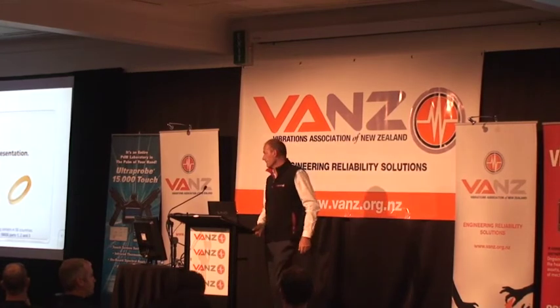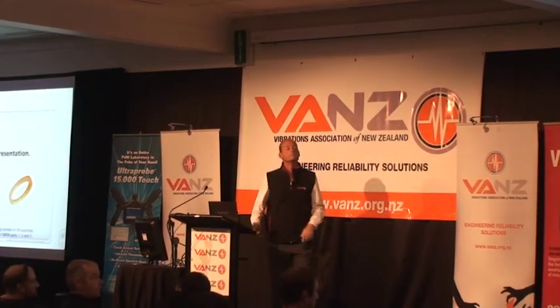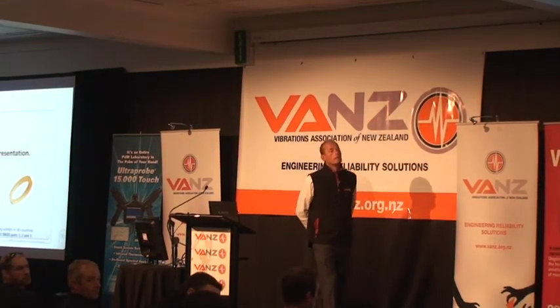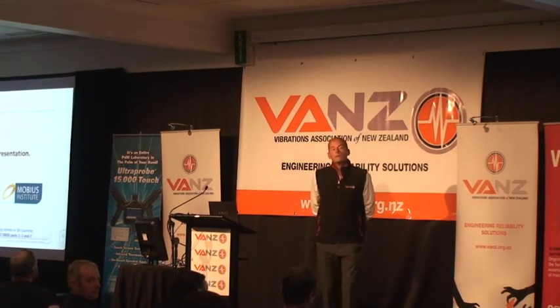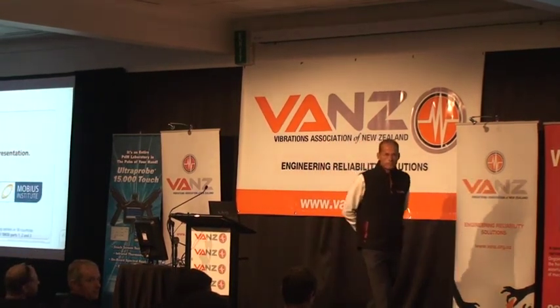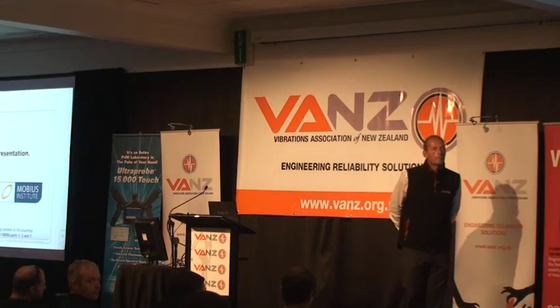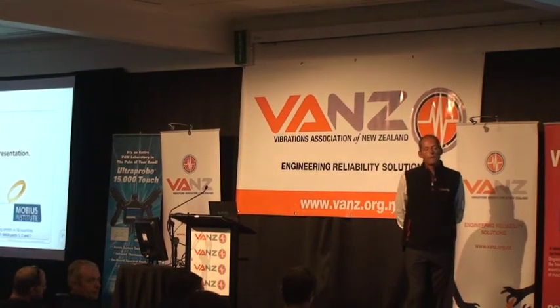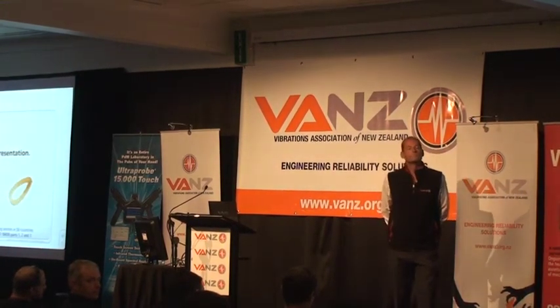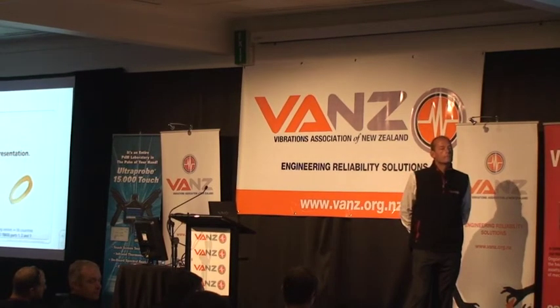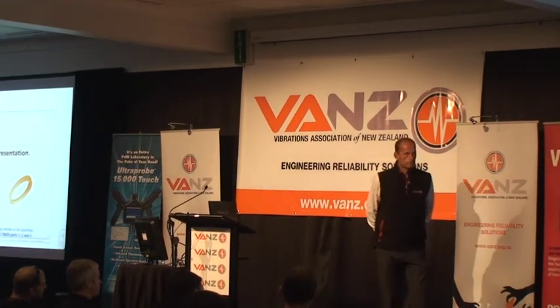Yeah, Jason, I've got a couple of comments. One is the positioning of the prox probe relative to the centre line of the bearing is quite critical, because if you've got one on the outboard end and one on the inboard end, you'll get a phase shift due to a bend. So you've got to make sure they're both in the same relative position and not on the neutral point through the bearing.